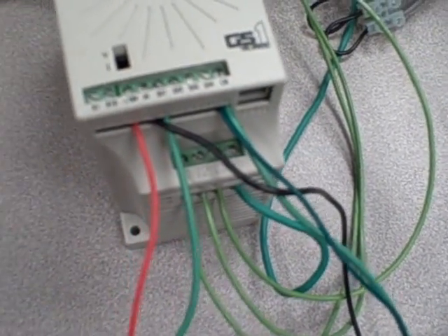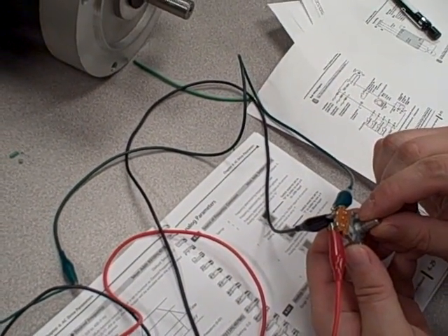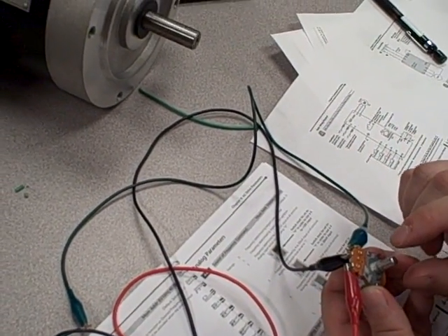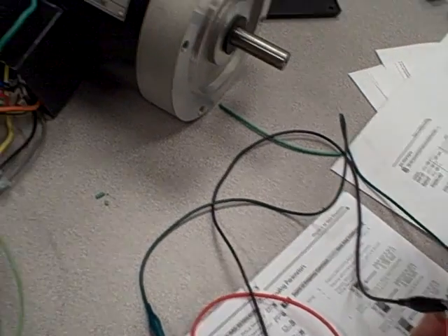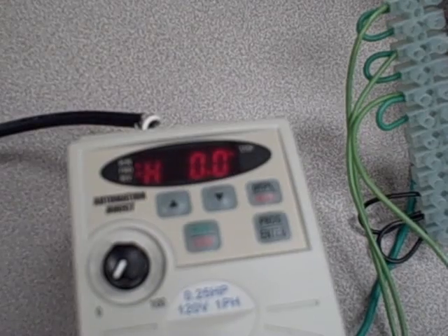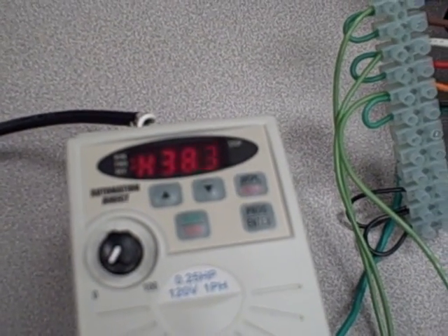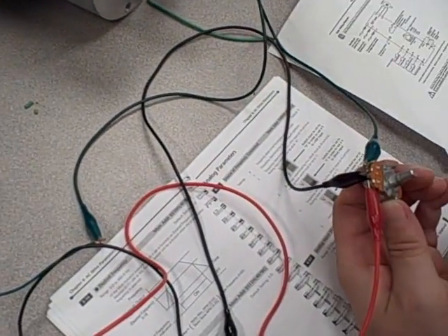And then by setting the proper parameter here, the analog parameter 4-00, setting that to use the voltage input, the 0 to 10 volt signal, we're now able to control the speed of the motor. So as Blake turns the knob of the pot, we can see the motor speed up and slow down. We can see the frequency right here, slowing down to 5 hertz, 0, it's stopped. Now as he turns it up, it accelerates. So it's got full control over the speed of the motor using a potentiometer.